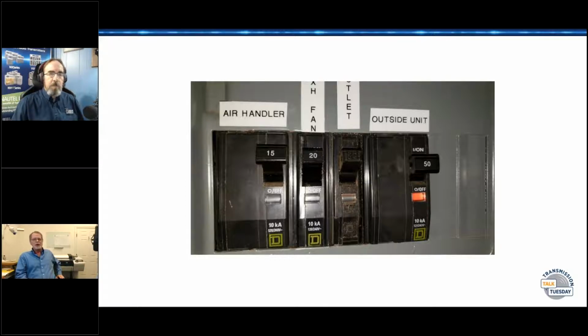And so I went walking around looking at all these sub panels, saw that breaker tripped. And it turns out that the compressor was burned up in that outside unit. And I would not have known it had I not looked over and seen that breaker. So it's like, okay, note to self, don't assume everything's working. Check, visualize every breaker. Well, that is a good lead into why we need to do a periodic swing by and look around visit.